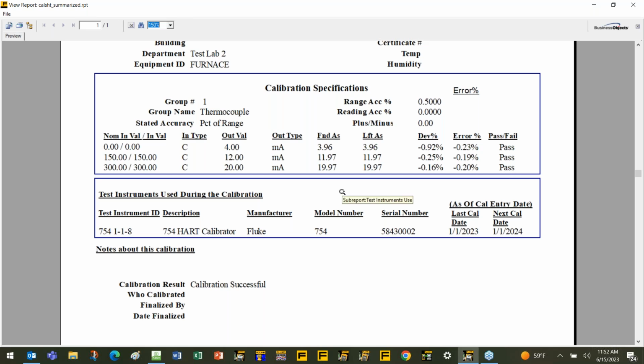The second box is also important, especially for audits, because this shows what test instrument was used during the calibration. Okay, so we used that 754 that we were just showing you, the serial number of it, and when the calibration was done and when it's due next. So calibration successful, and that is pretty much the test that we wanted to look at here.